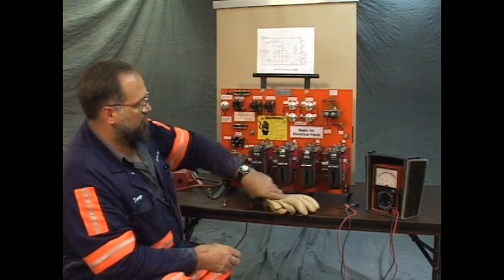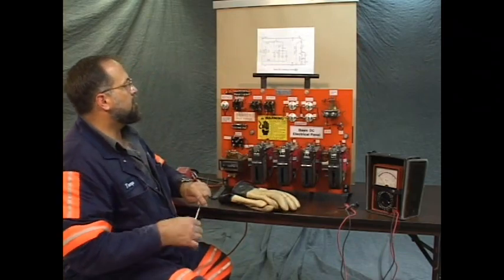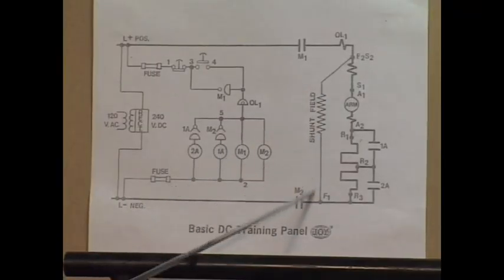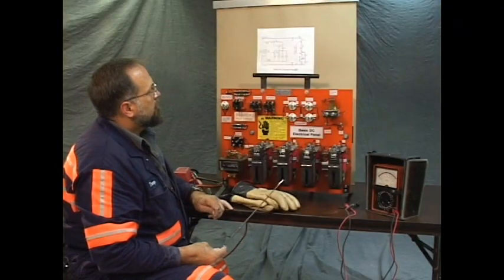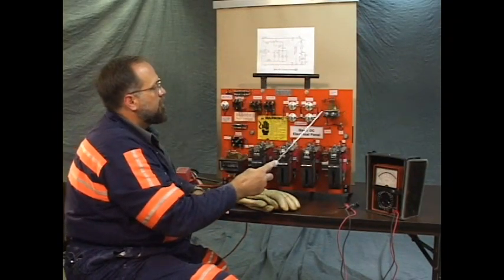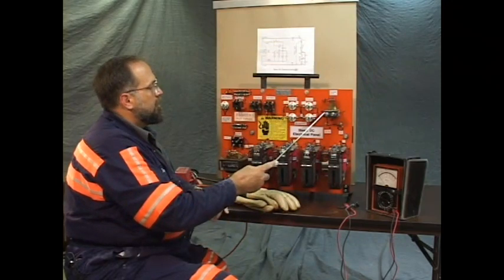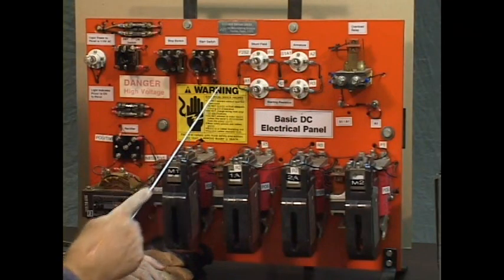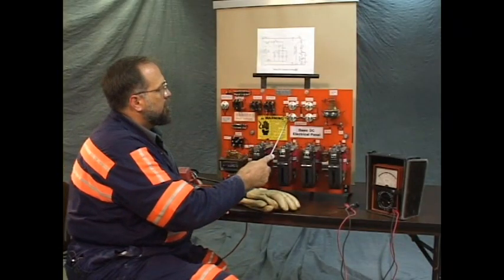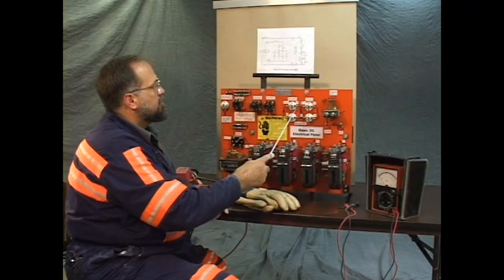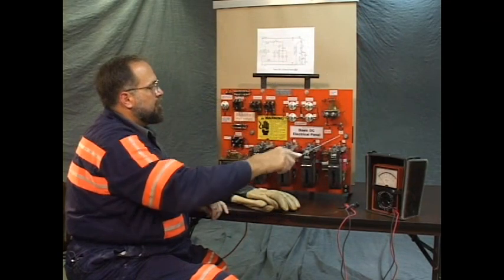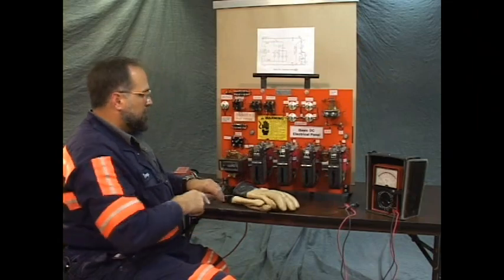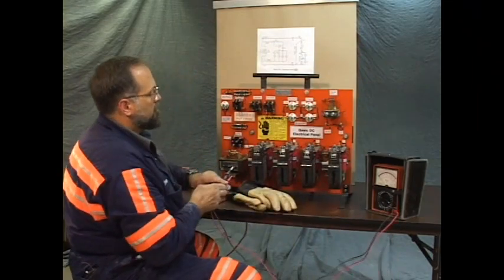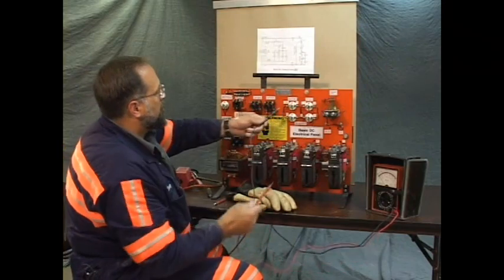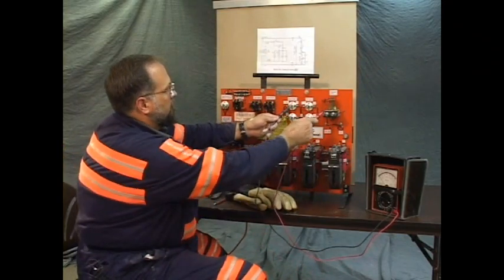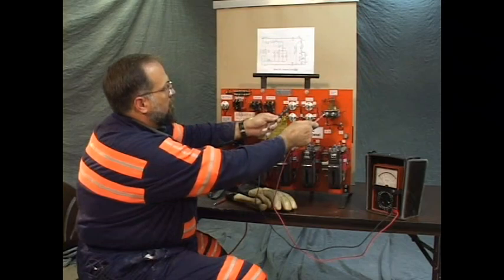As we illustrated earlier, we feel that our problem lies on only one part of the circuit, from here to here. And that F2, S2 point on OL1, that's this point right here. It should read little or no resistance from here to there. And if we have it there, this point here, the F1 point, should read little or no resistance from here to M2, right here in the back. Let's check those places. The first point, overload relay to the shunt field light. We don't have a circuit there.